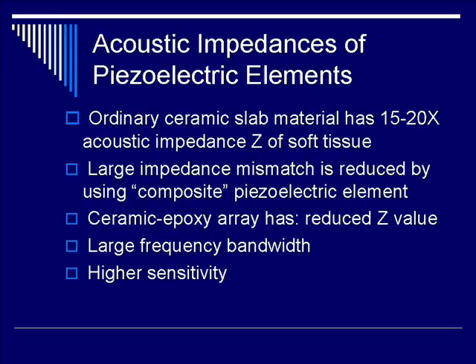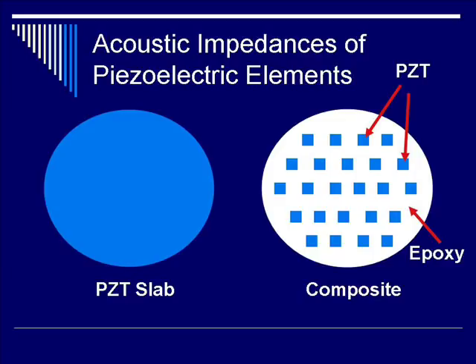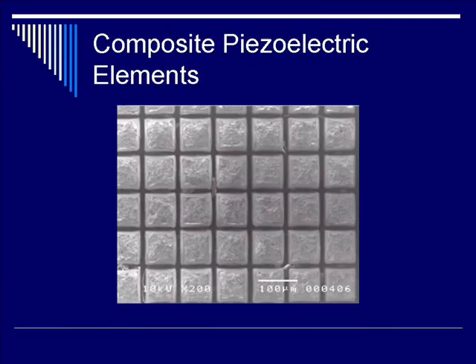Regarding acoustic impedances of piezoelectric elements: an ordinary ceramic slab has 15 to 20 times the acoustic impedance Z of soft tissue. This large impedance mismatch can be reduced by using a composite piezoelectric element, which consists of ceramic pillars surrounded by an epoxy array, resulting in a reduced Z value. It also provides a larger frequency bandwidth and higher sensitivity. A solid PZT slab has a Z of 30×10⁶ rayls, whereas composite material has a Z of only 10×10⁶ rayls. A micrograph shows an actual fabricated composite piezoelectric array consisting of multiple PZT pillars surrounded by insulation in the gaps.